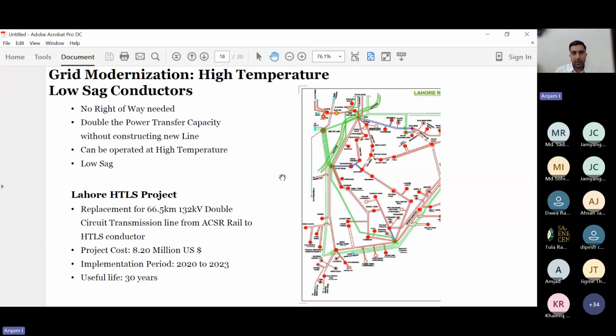So high temperature low sag conductors, as we already know, can use the same right of way corridors, and obviously we will not need to install new transmission towers. The only thing we need to do is change the hardware as well as the conductors on the existing transmission lines. So they enable you to carry almost double the power transfer of the existing transmission line without the need to construct a new transmission line.